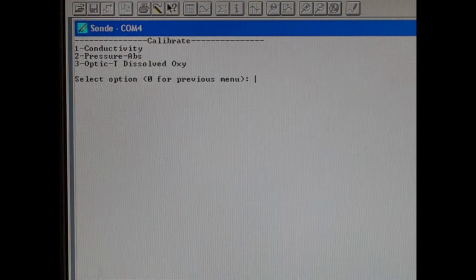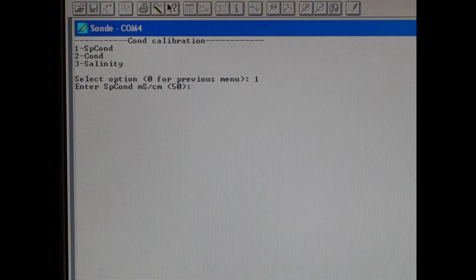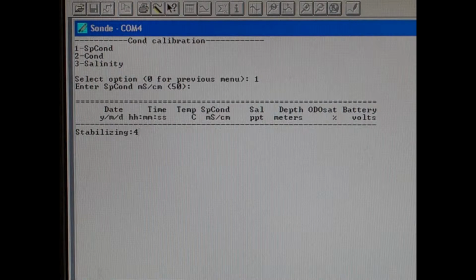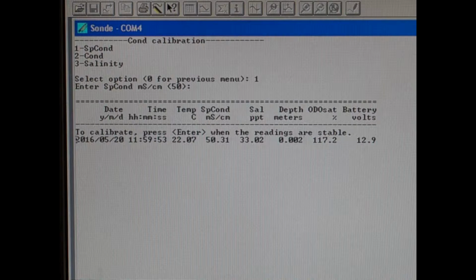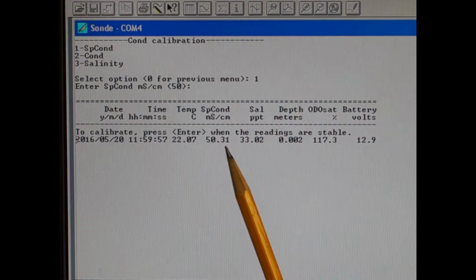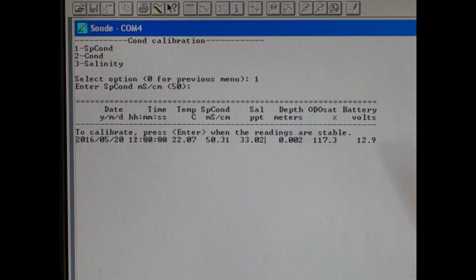Alright, now that we're back on the computer, then we go to conductivity from the calibration menu. And we're going to do SPCon, which is number 1. And enter the SPCon, that's our calibration value, which is, it's already 50, but it is 50. So we can either hit enter or we just push 50 and enter. So again, it's going to give us a reading of the Sonde. This is the pre-reading, and so right now the conductivity is 50.31 and the temperature is 22.07.